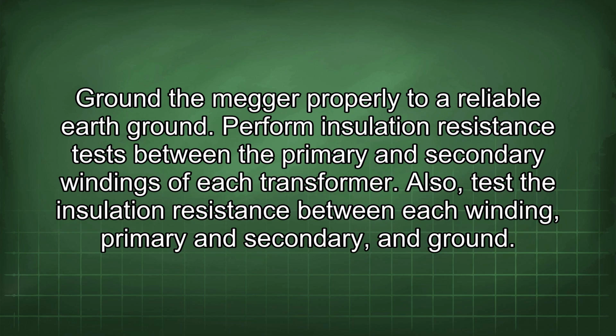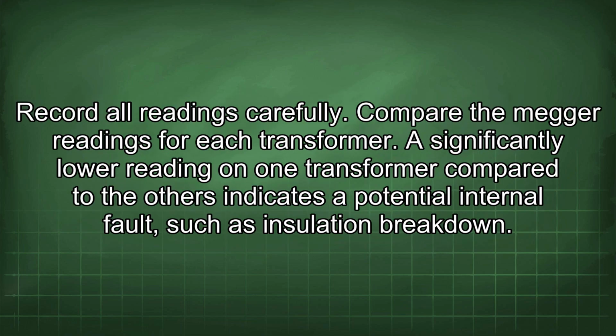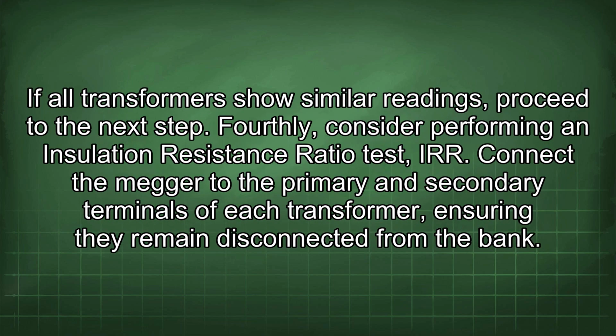Perform insulation resistance tests between the primary and secondary windings of each transformer. Also, test the insulation resistance between each winding, primary and secondary, and ground. Record all readings carefully. Compare the megger readings for each transformer. A significantly lower reading on one transformer compared to the others indicates a potential internal fault, such as insulation breakdown. If all transformers show similar readings, proceed to the next step.